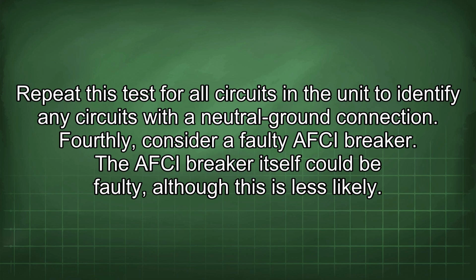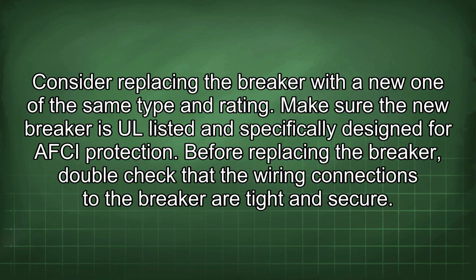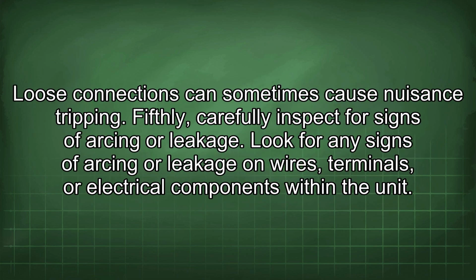The AFCI breaker itself could be faulty, although this is less likely. Consider replacing the breaker with a new one of the same type and rating. Make sure the new breaker is UL listed and specifically designed for AFCI protection. Before replacing the breaker, double-check that the wiring connections to the breaker are tight and secure. Loose connections can sometimes cause nuisance tripping.